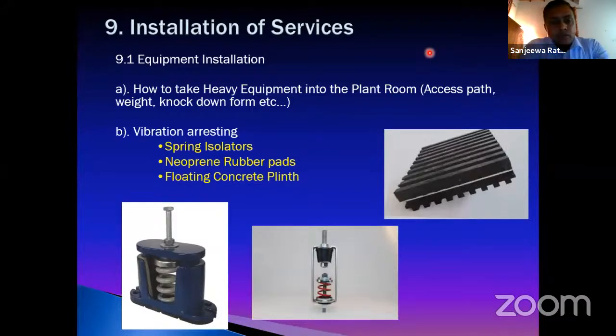Then the second one, vibration arresting. Heavy equipment or rotating equipment like pumps and motors are always generating vibration. So the vibration must be minimized or arrested, otherwise it becomes a hassle to all others. It may even be a danger to the building structure if you are not arresting it properly. So we use the spring isolators shown in this picture. The second one is also a spring isolator, which you mount into the ceiling or the soffit. Then this one is neoprene rubber pads, which are also used to arrest or minimize the effect of the vibration.